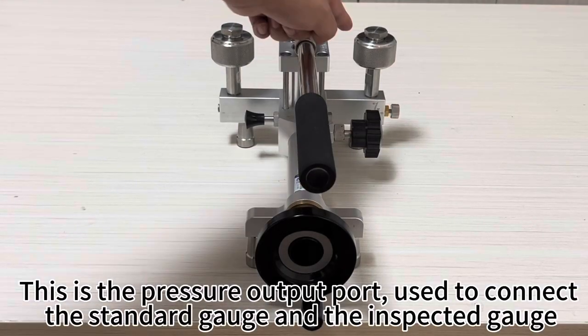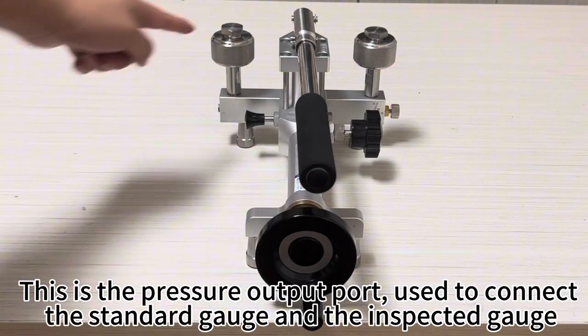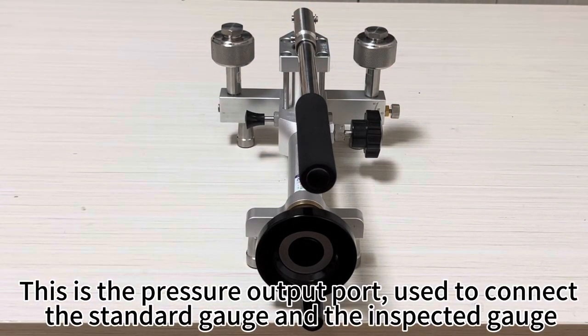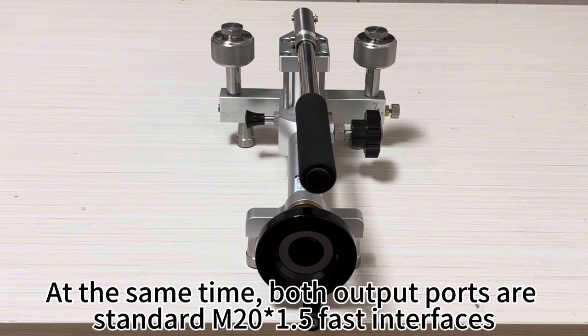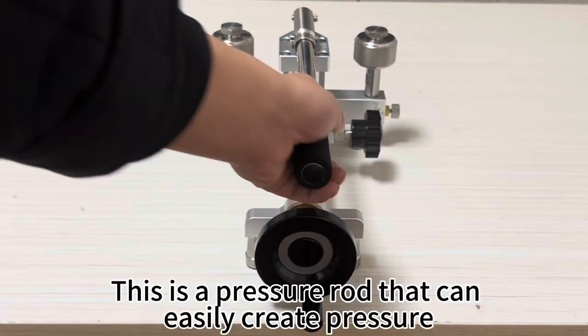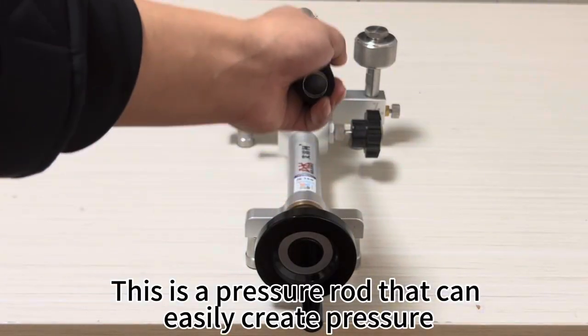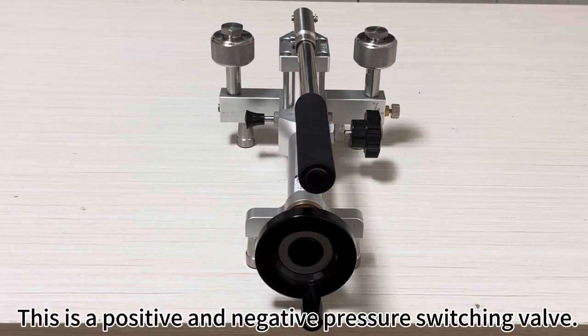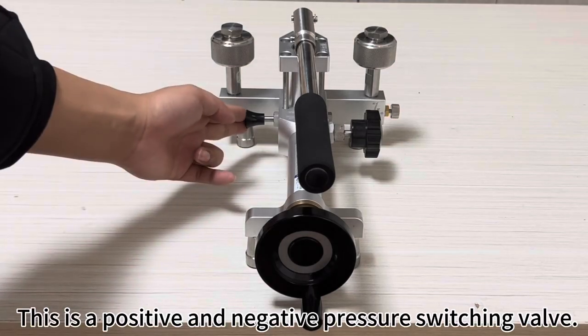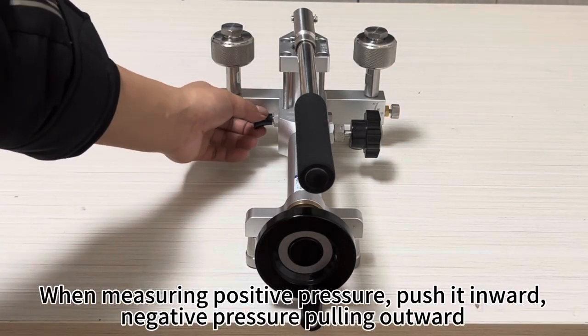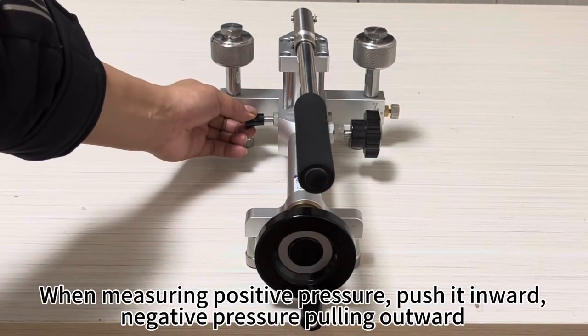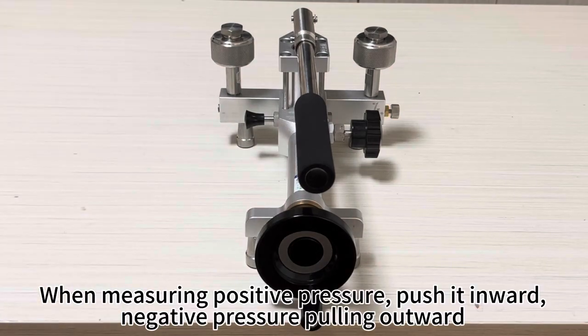This is the pressure output port, used to connect the standard gauge and the inspected gauge. At the same time, both output ports are standard M20 by 1.5 fast interfaces. This is a pressure rod that can easily create pressure. This is a positive and negative pressure switching valve. When measuring positive pressure, push it inward; for negative pressure, pull it outward.